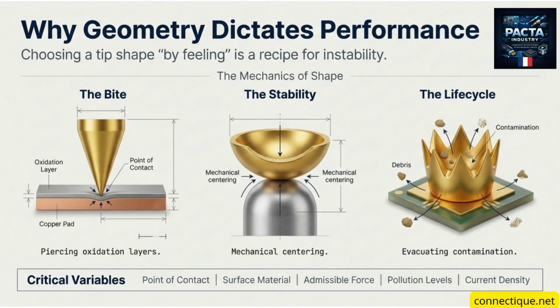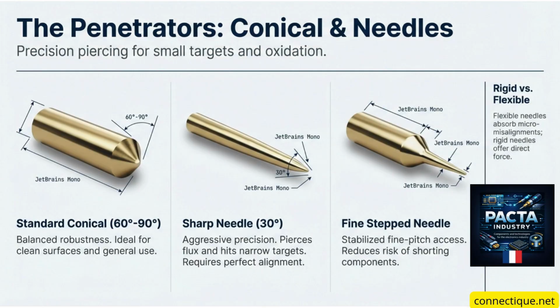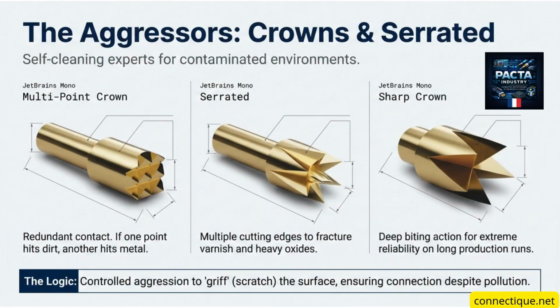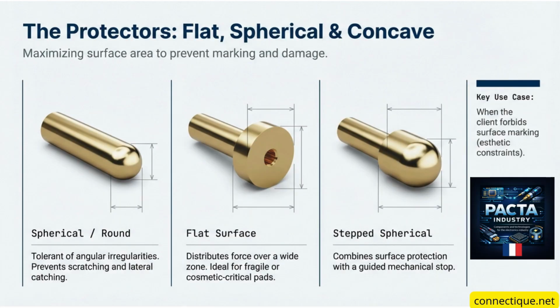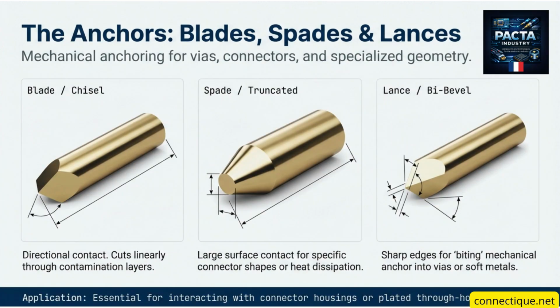But the trade-off has to be the same as the wide cone. Yeah. It can't clean itself. It's terrible at cleaning. If there is a speck of flux residue or dust on that pad, a round tip will just slide right over it. It won't pierce the film. So you get an open circuit error on a perfectly good board. Yes. You trade mechanical safety for higher preparation costs. You have to make sure your boards are squeaky clean before you can use the round tips.